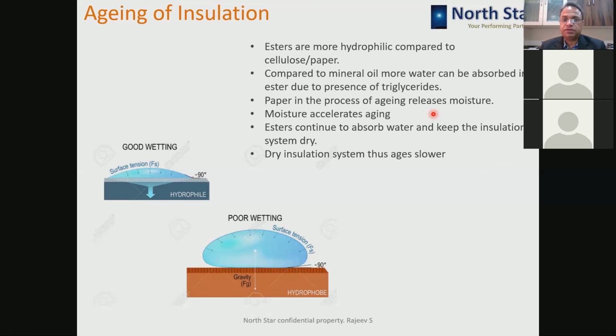But in the case of esters, because they are more hydrophilic compared to paper, all the moisture remains in the ester and very little moisture goes to the paper. So in ester-filled transformers, the insulation is drier compared to mineral oil-filled transformers. And as the insulation is drier, the dielectric properties and performance of the transformer will be much superior as compared to mineral oil transformers.